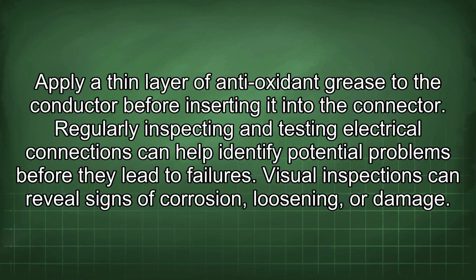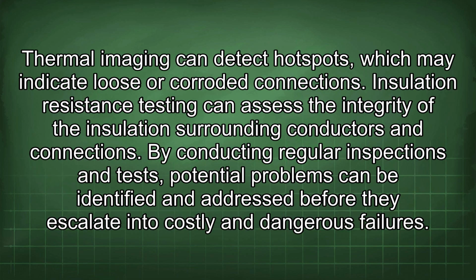Visual inspections can reveal signs of corrosion, loosening, or damage. Thermal imaging can detect hotspots, which may indicate loose or corroded connections. Insulation resistance testing can assess the integrity of the insulation surrounding conductors and connections.